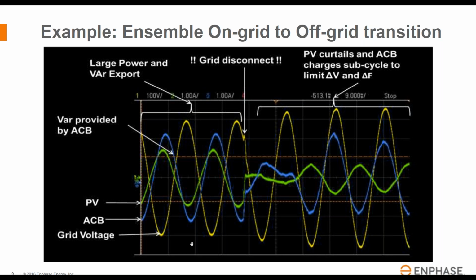So just to demonstrate how the system works, here's a waveform, a scope capture. The left-hand part of the slide is showing the system connected to the grid. You can see the yellow curve is voltage, and you can see that the voltage is a little bit low. And then about in the middle of the slide, you see that a disconnection occurs. So the system's now isolated from the grid. However, you see that the voltage ramps up slowly over the next couple of cycles and remains stable. And what you see there is the green line would be the power contribution from the PV array, and the blue line would be the power contribution from the AC battery. But you see it's virtually a transparent transition. Next slide, please.